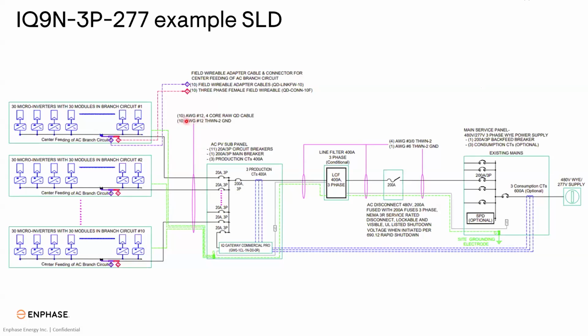Right here, you can see it says raw QD cable for your home runs back to the panel. You can utilize the raw QD cable to go right from that center tap adapter to pull your home run and run that back to your combiner panel, depending on that distance. You have to keep in mind, though, that there are only number 12 size conductors in that QD cable. So if you're installing that combiner panel a long way away, you might want to transition over at some point near the array into conduit and upsize that wire so you don't have any overall voltage rise issues.